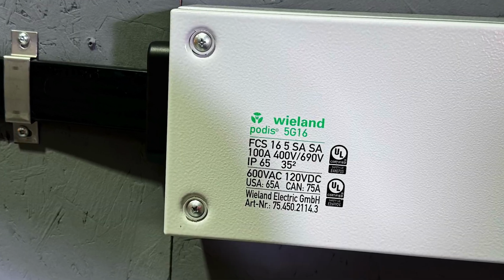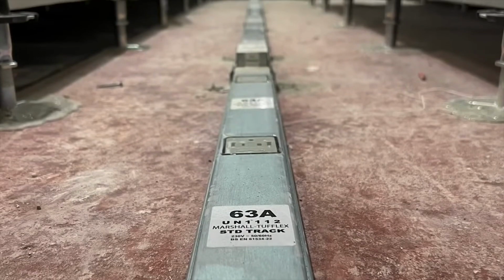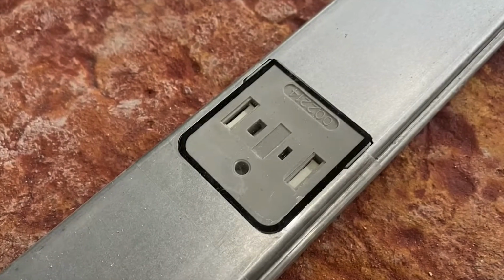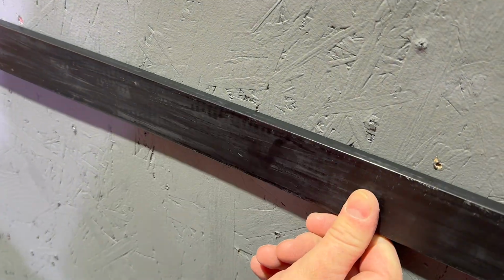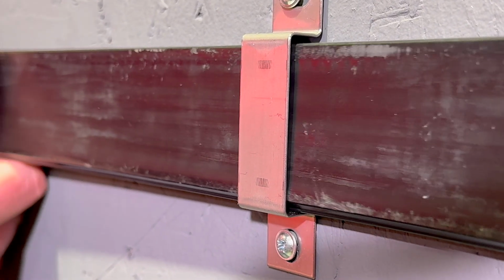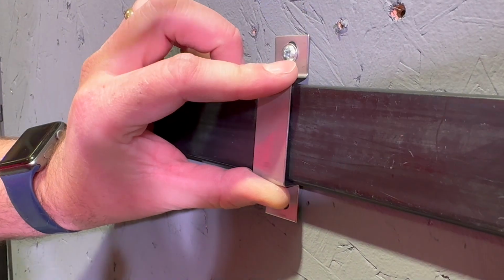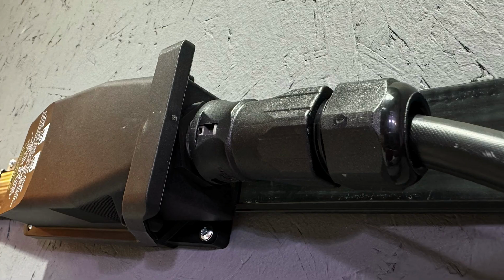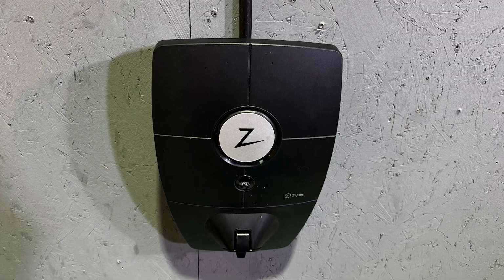It's an approach that will be familiar to electricians who fitted busbar trunking in factories or underfloor busbar trunking in offices. The flat cable serves as a busbar designed to be mounted directly onto the ceiling or walls of the car park. At designated charge points, tap-off boxes securely clamp around the cable, facilitating a connection to each electric vehicle charger.